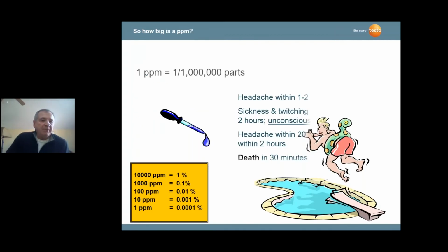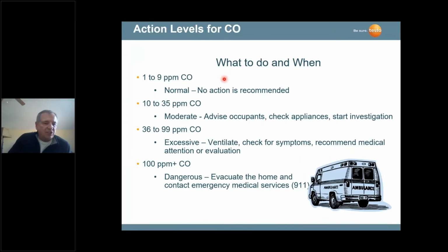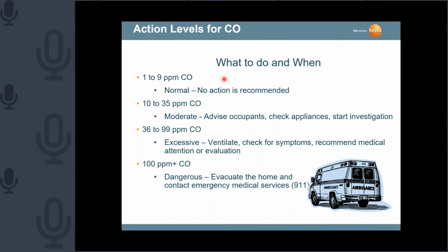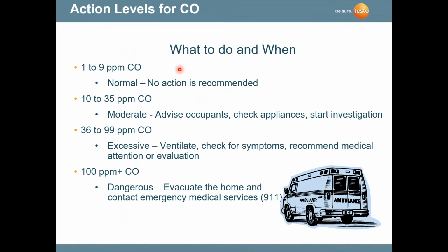So here's some ambient air conditions, as I indicated to you previously. Typically, furnace burner manufacturers want to maintain no more than 100 ppm. You may have some local protocols, but 1 to 9 ppm, 10 to 35 ppm is moderate. These are ambient air conditions. When you get over 100 ppm CO, that's a very dangerous possibility. You've got to evacuate the home immediately.